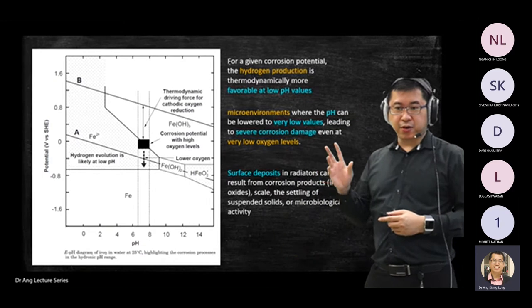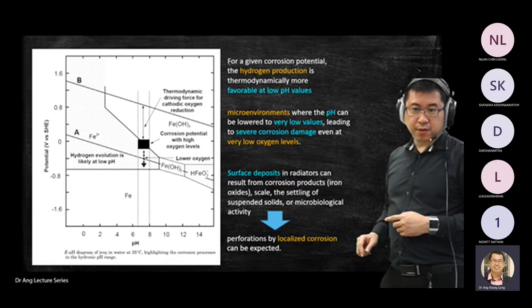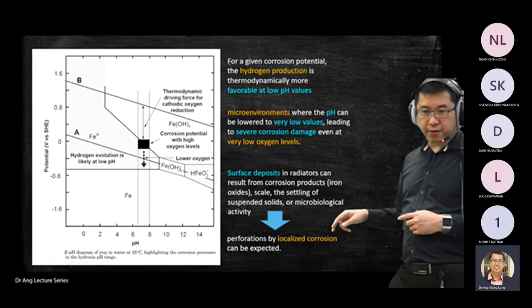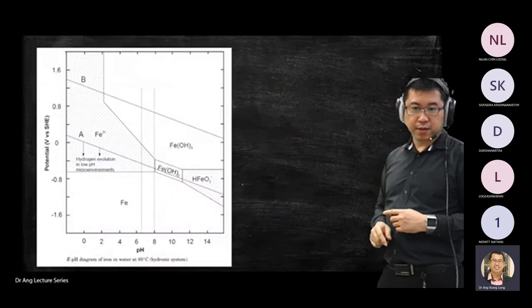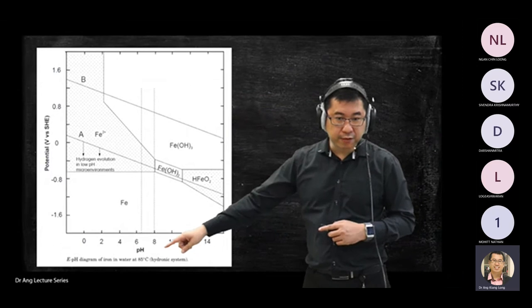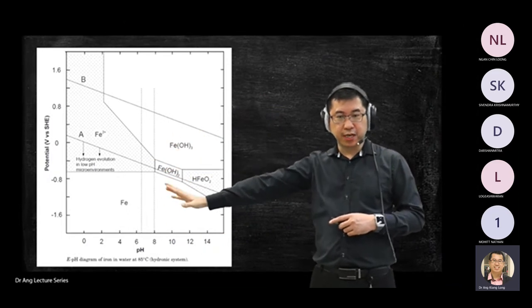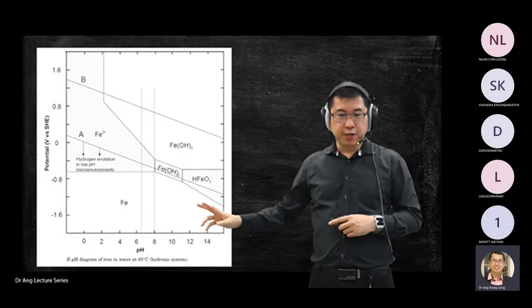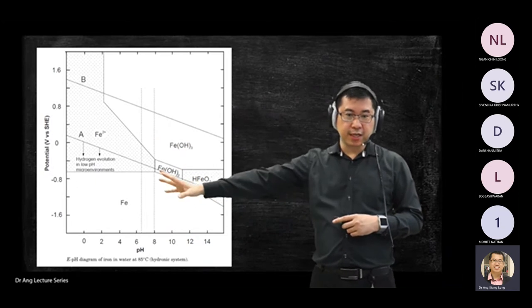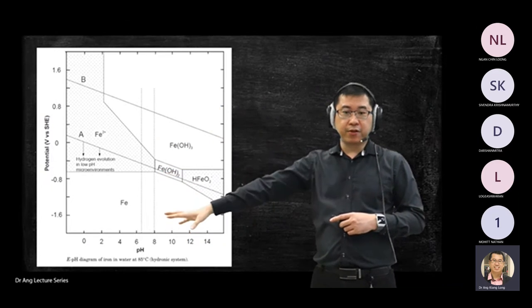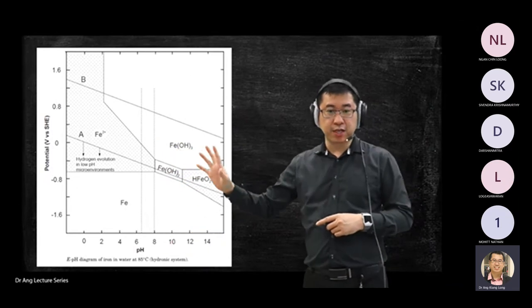When corrosion happens in the radiator, you will see a chocolate or orange color. There is a diagram for 85°C — there is an E versus pH diagram (potential versus pH diagram) for that temperature. When you read an E-pH diagram, you have to be careful about temperature because different temperatures give different settings. You cannot take the 25°C case to analyze cases at 85°C — you must use the correct graph.